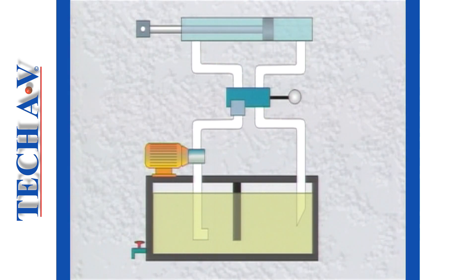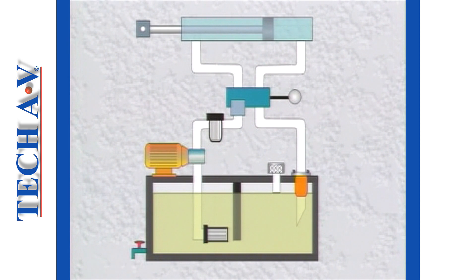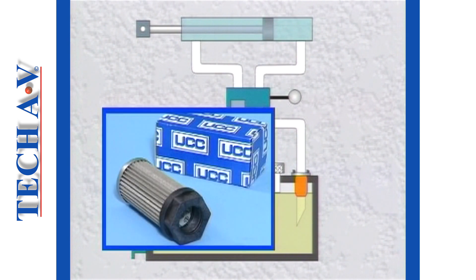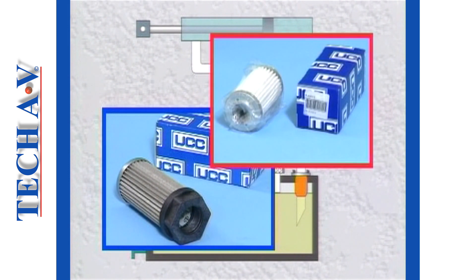To summarise, a system is protected from the harmful effects of dirt by using various strainers and filters. Strainers are normally installed on suction lines, whilst filters are fitted into the pressure and return lines. The primary purpose of a strainer is to protect the pump by trapping relatively large particles. The primary purpose of a filter is to trap small dirt particles, thus preventing damage to control valves and sludge formation in the tank.